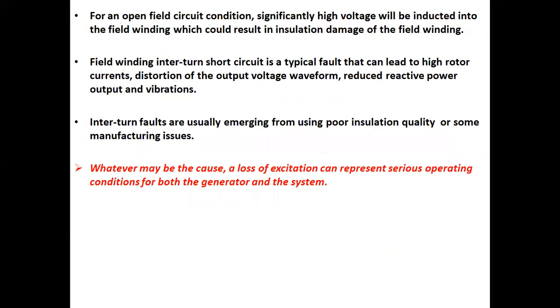For an open field circuit condition, a significantly high voltage will be induced into the field winding, which could result in insulation damage of the field winding. Field winding inter-turn short circuit is a typical fault that can lead to high rotor currents, distortion of the output voltage waveform, reduced reactive power output, and vibrations. Inter-turn faults are usually emerging from using poor insulation quality or some manufacturing issues. Whatever may be the cause, a loss of excitation can represent serious operating conditions for both the generator and the system.